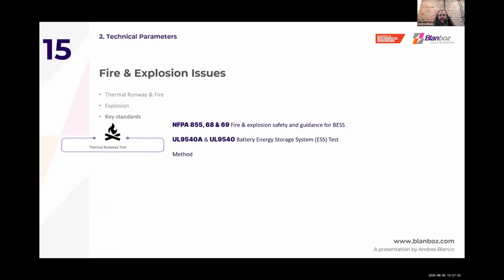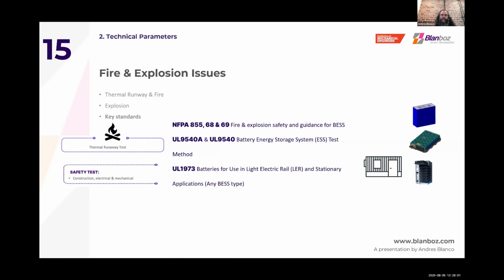Then we get other American standards that have been widely used, the UL 9540A test methodology and the UL 9540 certifications. What these tests do is try to see the thermal runaway between the different components in a battery system. You start by burning the cell. If the fire propagates, you go to the module, so the racks, and then finally your container. Also important, UL 1973: these are certifications and tests done at battery cell level. Then you have your UN 38.3, which are safety tests done on the batteries to be able to transport them either by sea, air, or land.